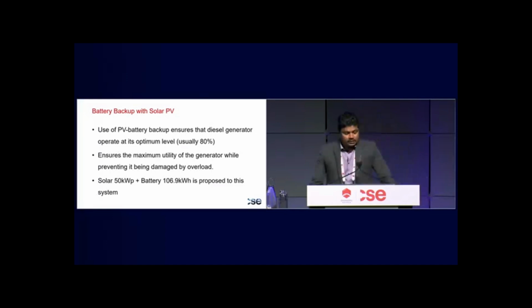As I mentioned earlier, the generators at that resort were 450 kVA, which translates to 360 kilowatts. The optimum level is to maintain these generators at 80%, which is around 300 kilowatts. The plan is to ensure maximum utility of the generator while preventing it from being damaged by overload, so you have to make sure it doesn't go into overload.